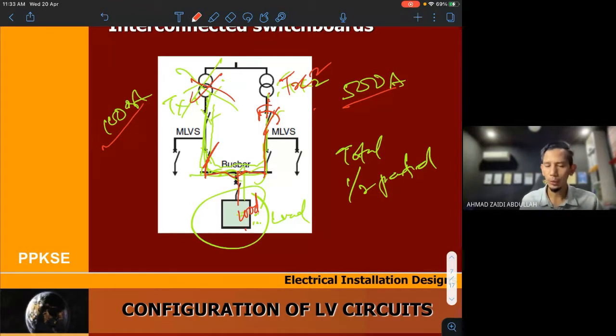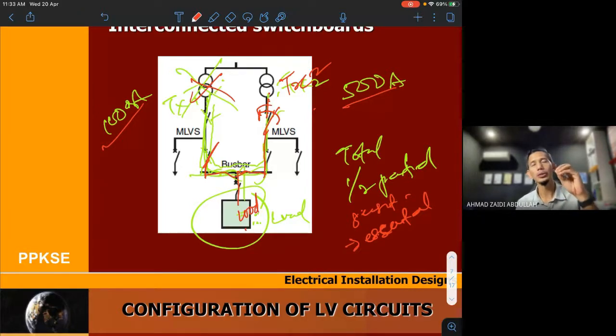So that's why normally when you are dealing with the genset, you must consider the essential load, meaning you need to decide which part is very important, which circuit, the important load. So you need to decide which one. For example, in your house, in your room, which has two sockets. Between the two sockets you need to decide which socket is the essential category. Essential means that when we are tripping, we have a failure from the main supply, the other supply will be connected and try to bring another source, another supply. We want something like that, a backup supply, but we just select which one is very important.